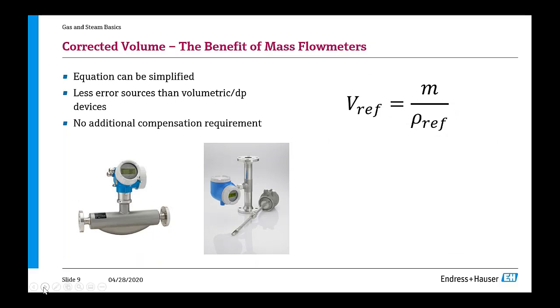The beauty is, if you're now using a mass flow meter, the world becomes much easier, because that corrected volume is now mass divided by the reference density. This reference density, you either know, because it's a gas that doesn't change its composition, so you just divide the mass by the reference density, or you read it in from a gas chromatograph at the inlet of your combined cycle power plant.